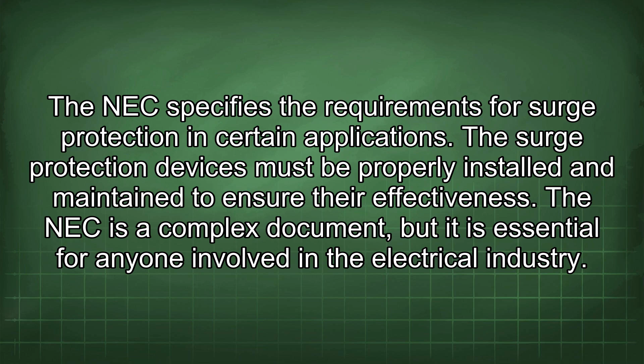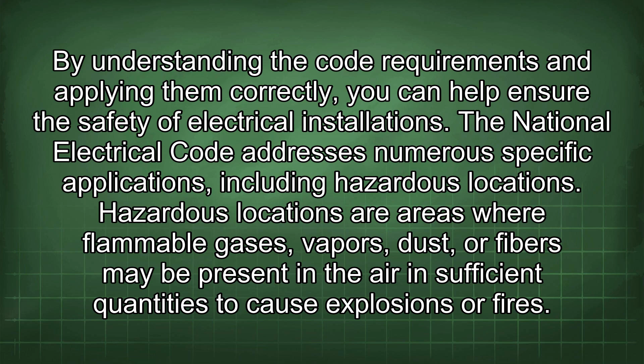The National Electrical Code addresses numerous specific applications, including hazardous locations. Hazardous locations are areas where flammable gases, vapors, dust, or fibers may be present in the air in sufficient quantities to cause explosions or fires. The NEC classifies hazardous locations into different classes and divisions based on the type of hazardous material and the likelihood of its presence. Class 1 locations are those where flammable gases or vapors are present.